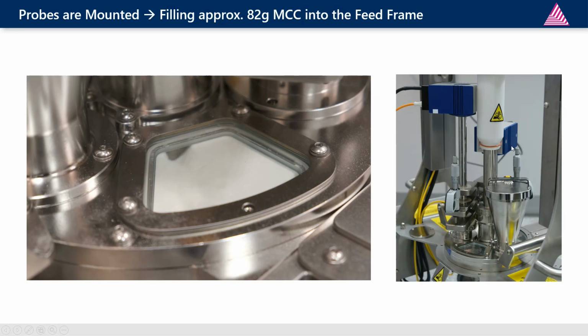All the time they were measuring simultaneously in the process, which also tells us we can either do model development on two units in parallel, or it is also possible to use two different probes on the feed frame simulator to either compare different technologies like NIR and Raman, or two different instruments or sensors, or, like in our case, to look at transferability of methods, etc.